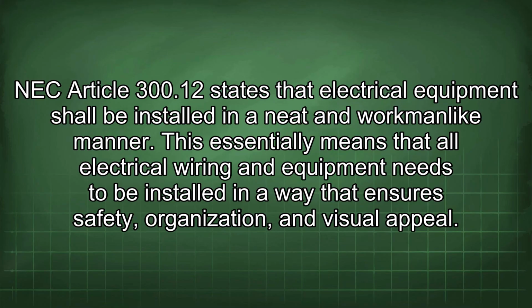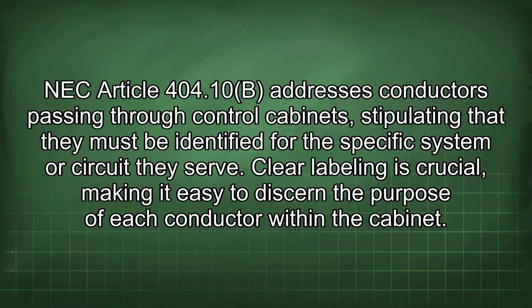NEC Article 300.12 states that electrical equipment shall be installed in a neat and workmanlike manner. This essentially means that all electrical wiring and equipment needs to be installed in a way that ensures safety, organization, and visual appeal. NEC Article 404.10b addresses conductors passing through control cabinets, stipulating that they must be identified for the specific system or circuit they serve. Clear labeling is crucial, making it easy to discern the purpose of each conductor within the cabinet.